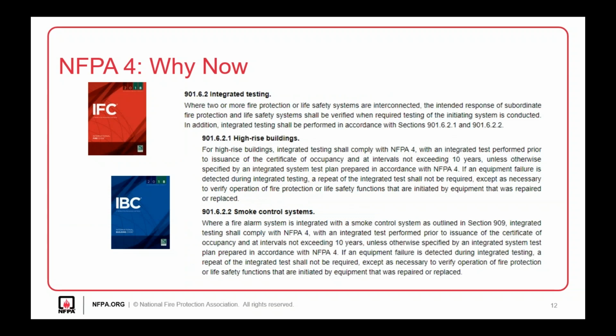I want to talk about the requirements in the building code. They're similar to NFPA 101 and 5000, saying you need to test the response of any integrated systems during testing, and that you need to do it per NFPA 4 if you have a high-rise building or a building with a smoke control system. So there's going to be a need for integrated testing on projects from jurisdictions that adopt any of these codes.